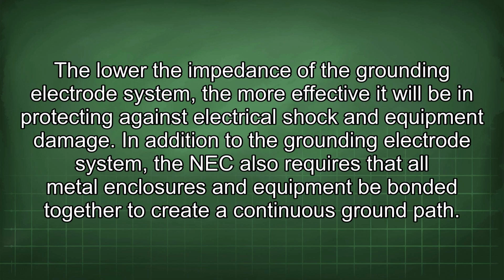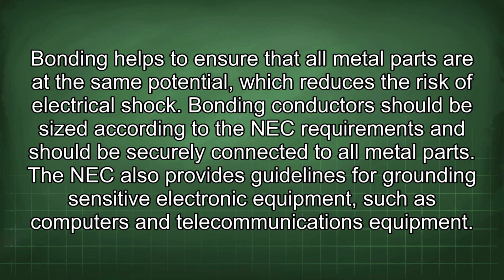The lower the impedance of the grounding electrode system, the more effective it will be in protecting against electrical shock and equipment damage. In addition to the grounding electrode system, the NEC also requires that all metal enclosures and equipment be bonded together to create a continuous ground path. Bonding helps to ensure that all metal parts are at the same potential, which reduces the risk of electrical shock.